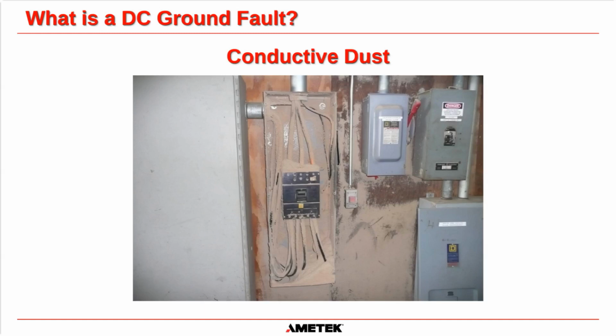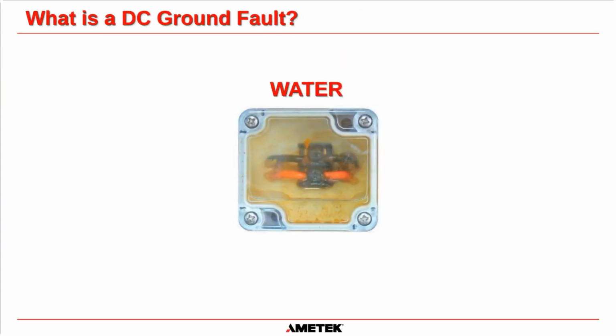Conductive dust. Obviously, this is a very extreme example, and I'm guessing this is a sawmill of some sort. But you can see there is a whole pile of sawdust down there, and that's the most concerning ones here. You can see there is sawdust resting across these terminals here. And if that gets some moisture in it and becomes conductive, that is a direct short between those two or three cables there. Okay, so that's a good example of dust, although it's a very excessive example of how dust can affect a system.